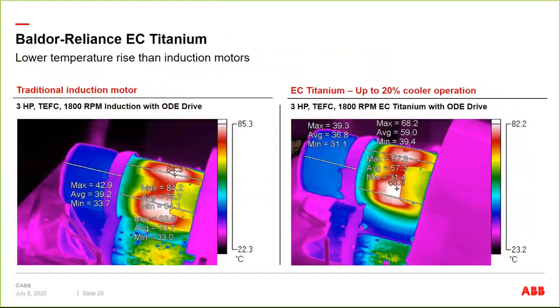This is just a thermal image. We don't need to spend a lot of time on this. Just the motor thermals. You can see it's much cooler running, about 20% less heat generated. That just gives you longer life of electrical components within the product. This is an equivalence test, meaning we ran it with the same drive on the back end of the motor. This is an induction motor, and this is the EC Titanium.